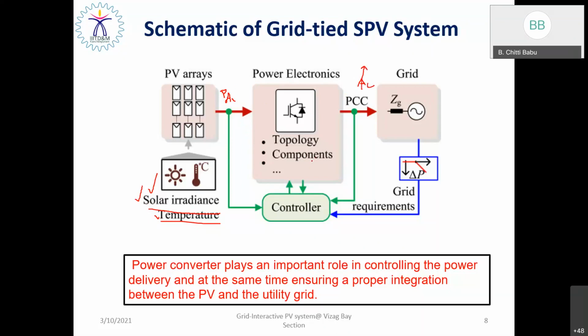So how do these power electronics converters ensure proper grid integration by satisfying the grid connection requirements? As I said earlier, grid connection requirements include active and reactive power control for frequency and voltage control, power quality, grid synchronization, and excellent dynamic response. These are all important requirements. So in order to achieve the grid connection requirements, we use a controller. We are going to design a very robust, very adaptive controller on this power electronics converter so that we can integrate solar photovoltaics with the utility grid very successfully. Power electronics converters provide an asynchronous interface. Please remember that. The power converter plays an important role in controlling the power delivery, and at the same time it ensures proper integration between the solar PV and the utility grid. So the heart of a grid-tied solar PV system is the power electronics converter and its control.